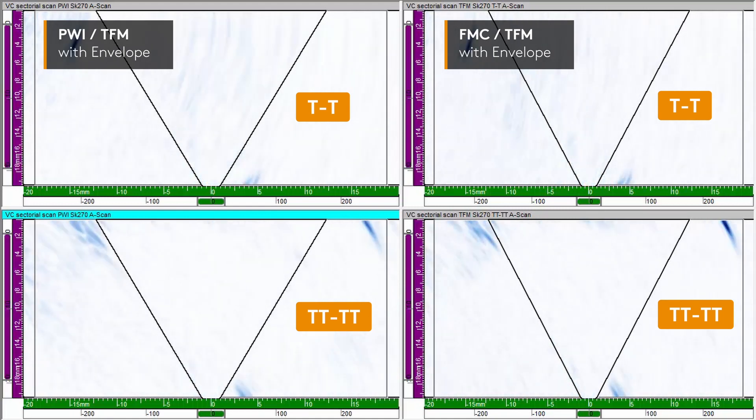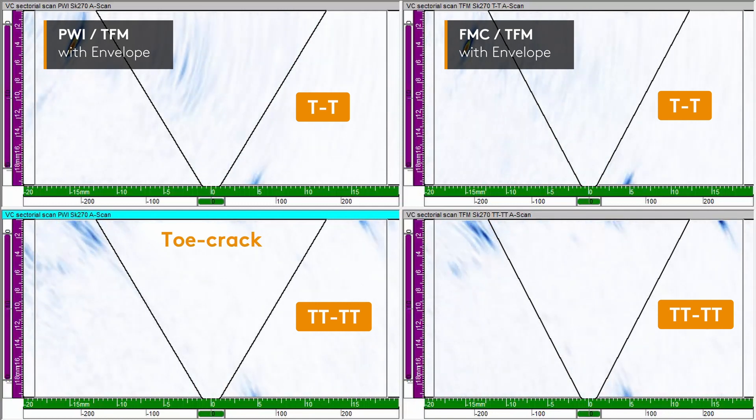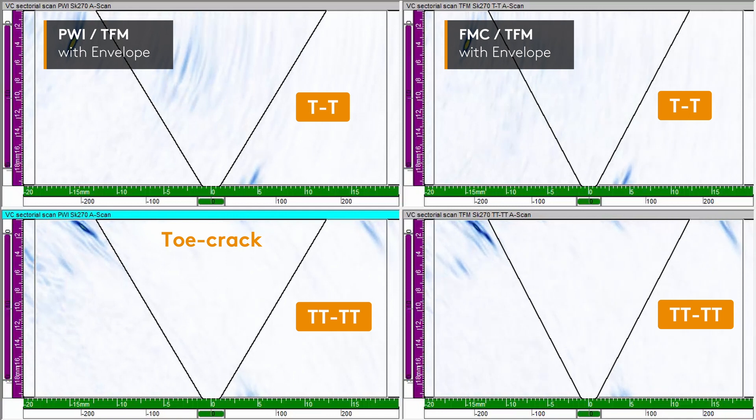The three realistic flaws in the weld specimen, a lack of fusion, an incomplete penetration in the root, and a toe crack are clearly detected and visualized.